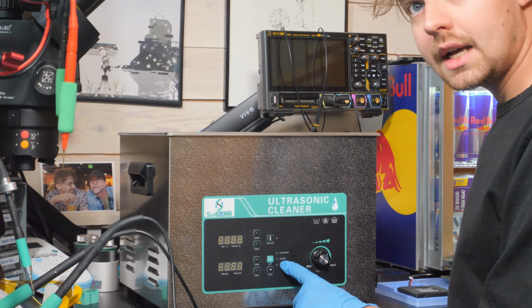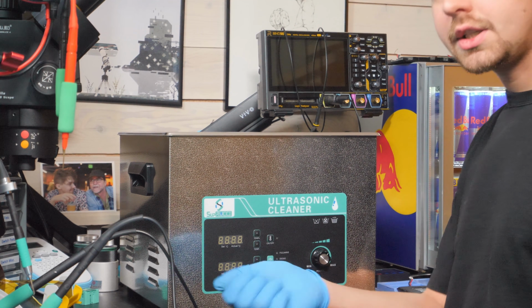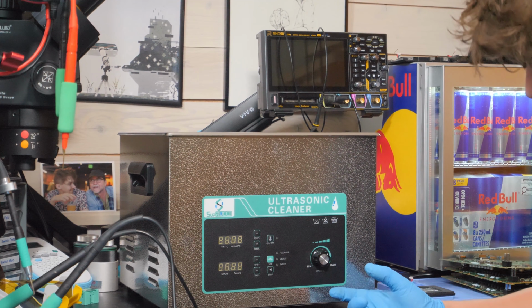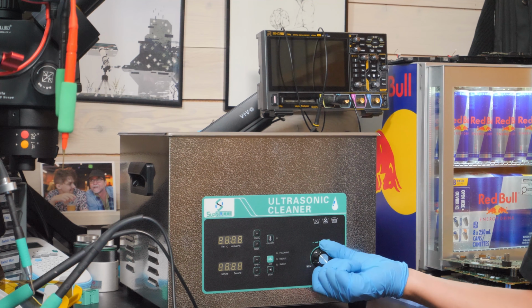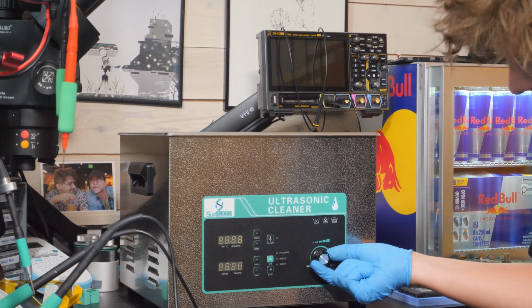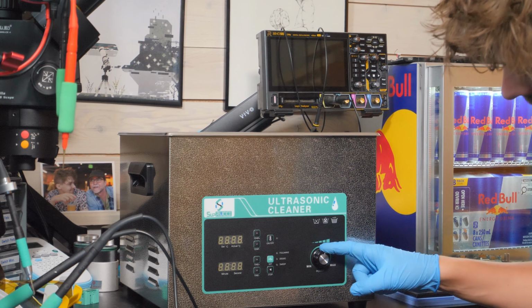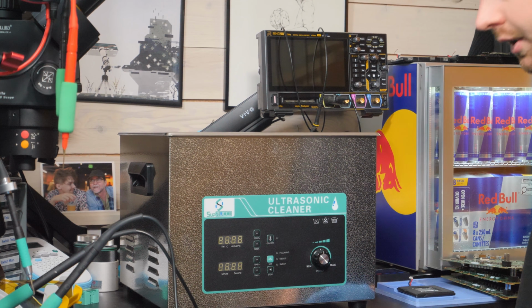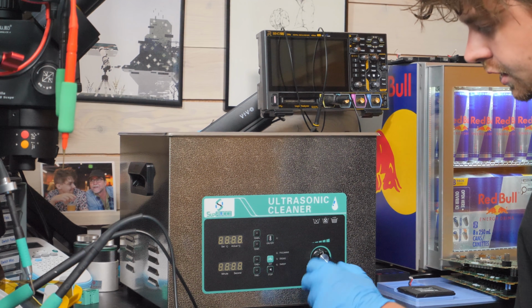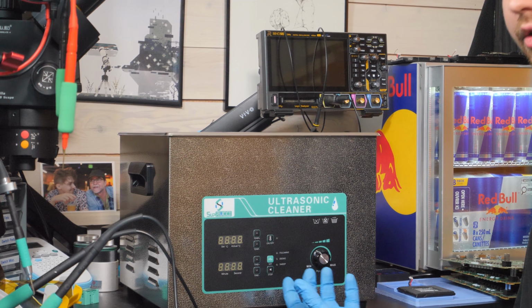I don't actually have a degas function on my other unit. They just tell you to run it for like 10 minutes. And a very cool feature that this has that the other one doesn't, and that even this unit does not appear to have, is a power knob here. So this allows us to adjust how strong the cavitation is. Likely it's adjusting how much voltage is going into the transducers under the tank.